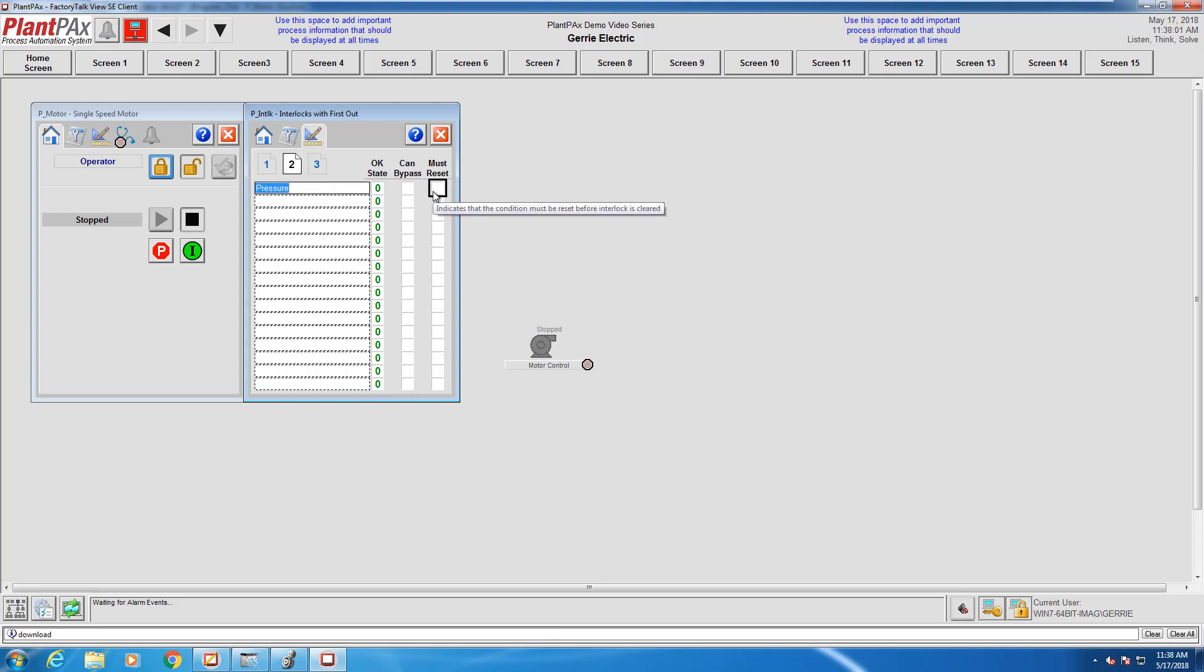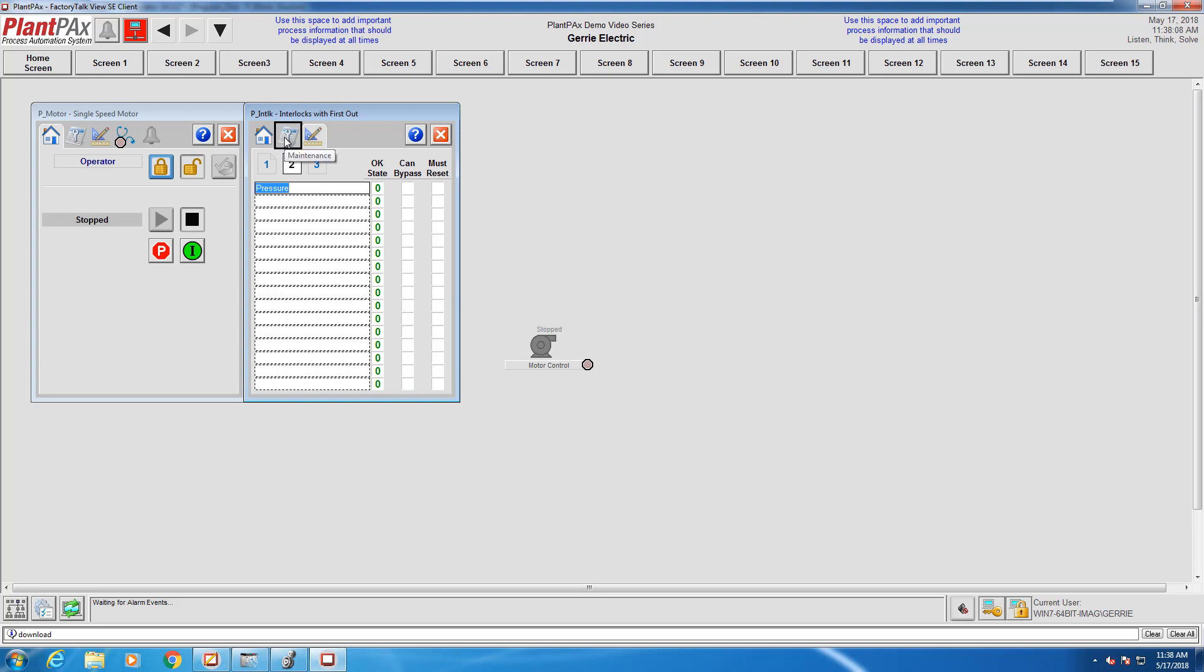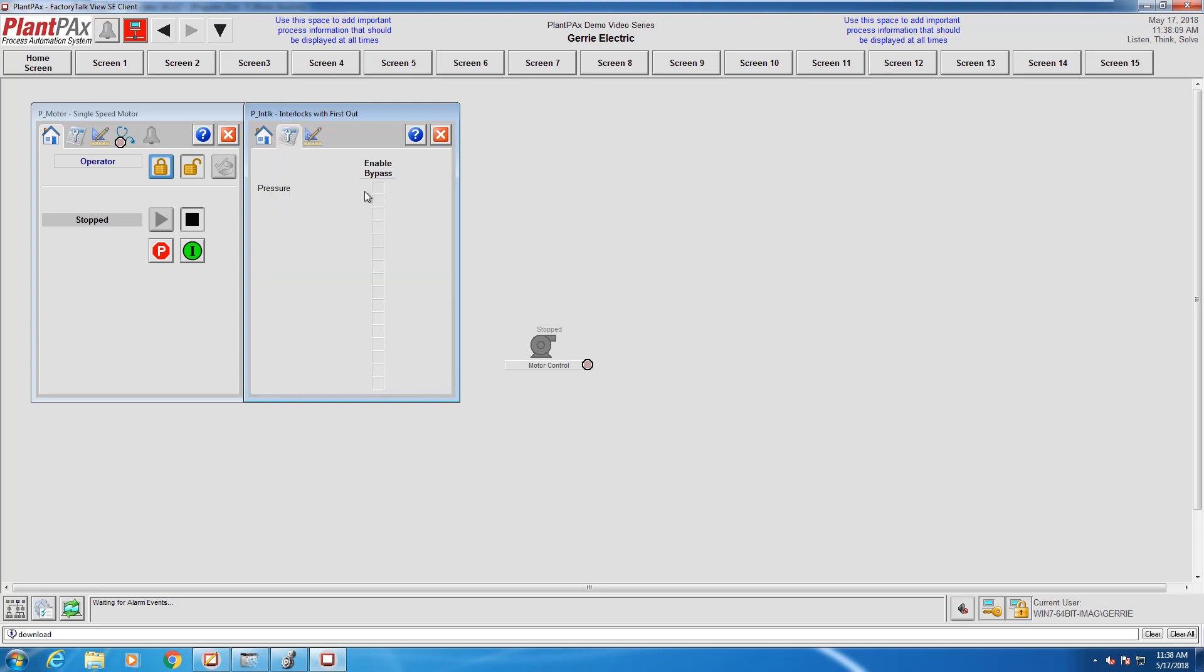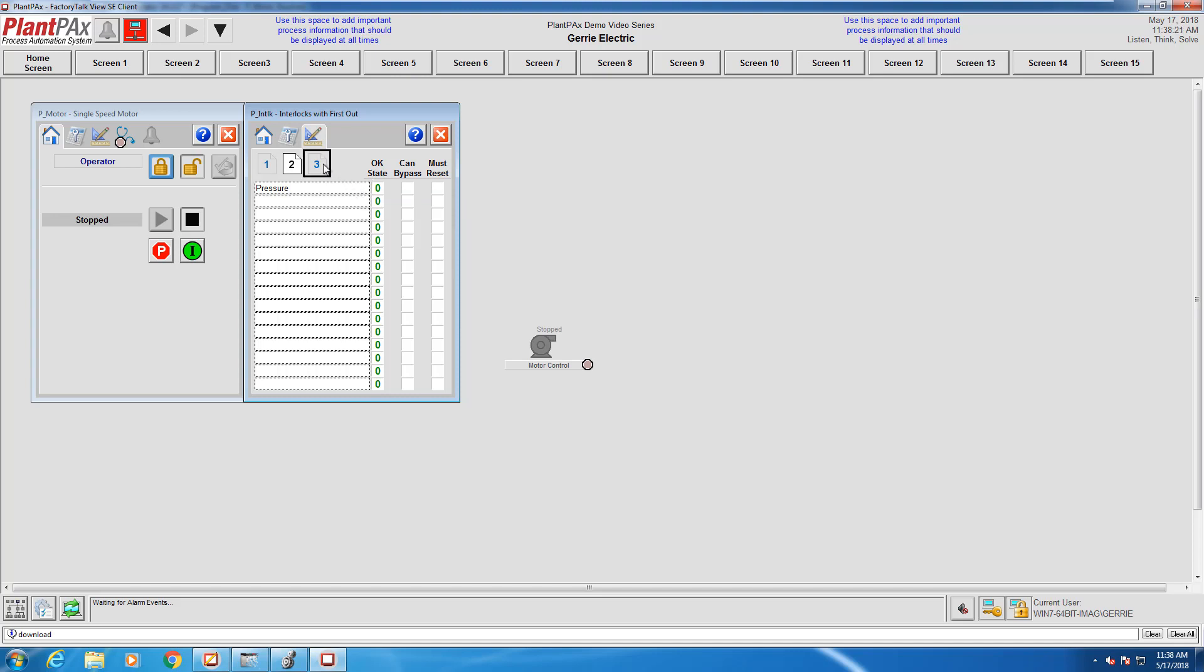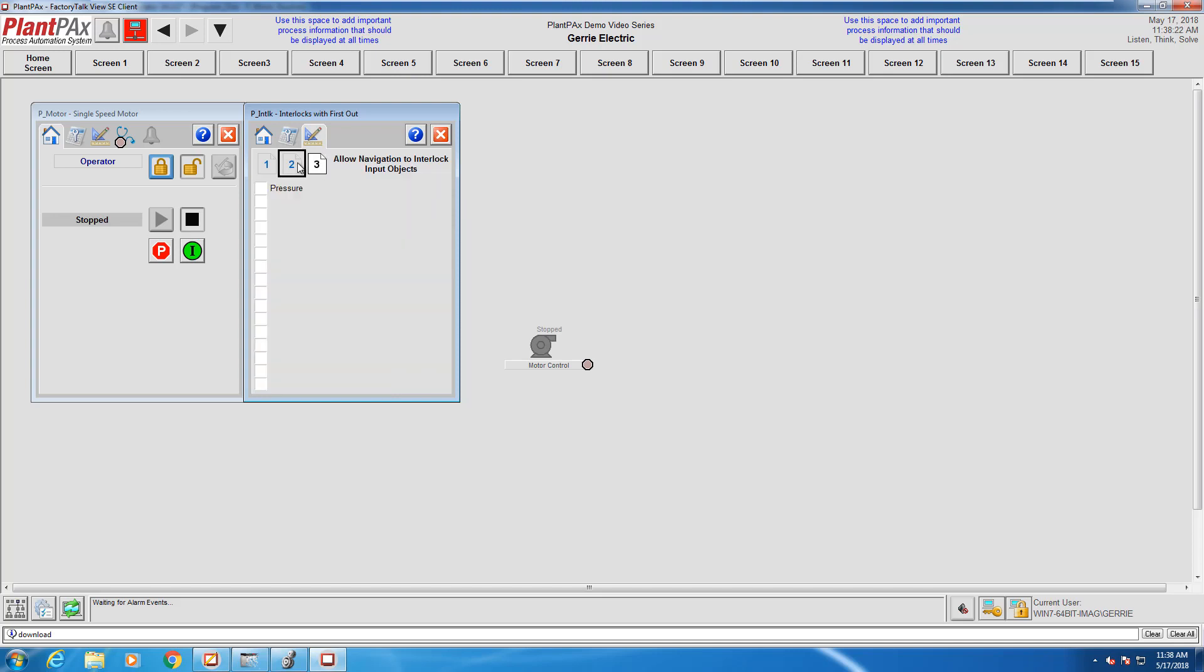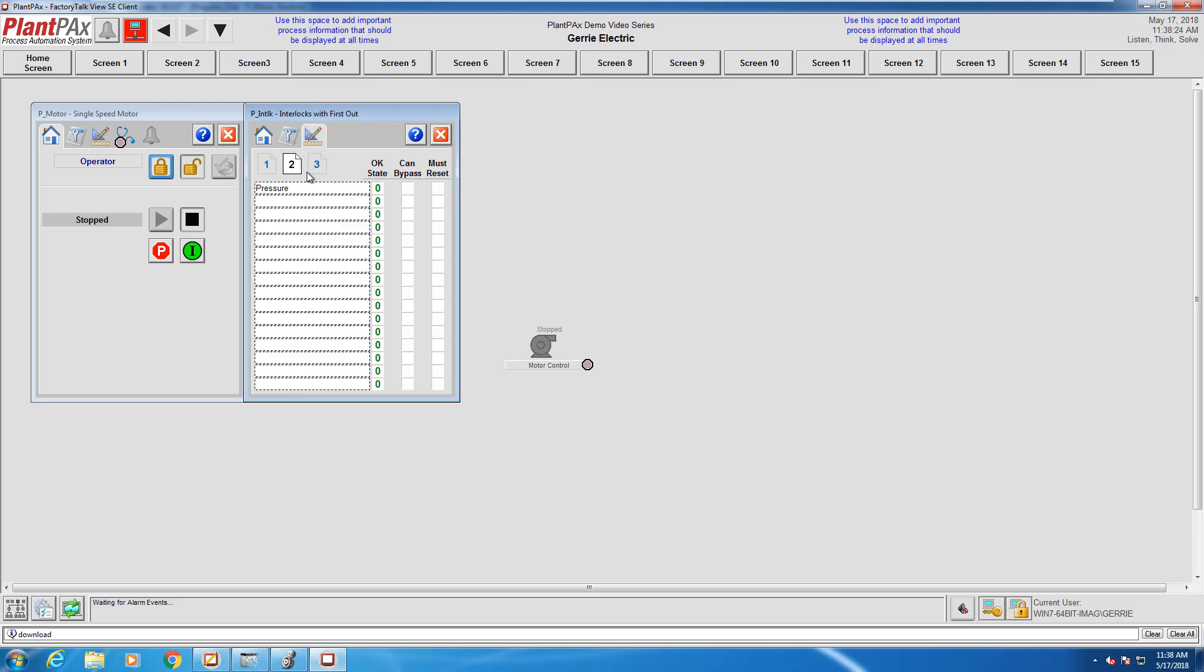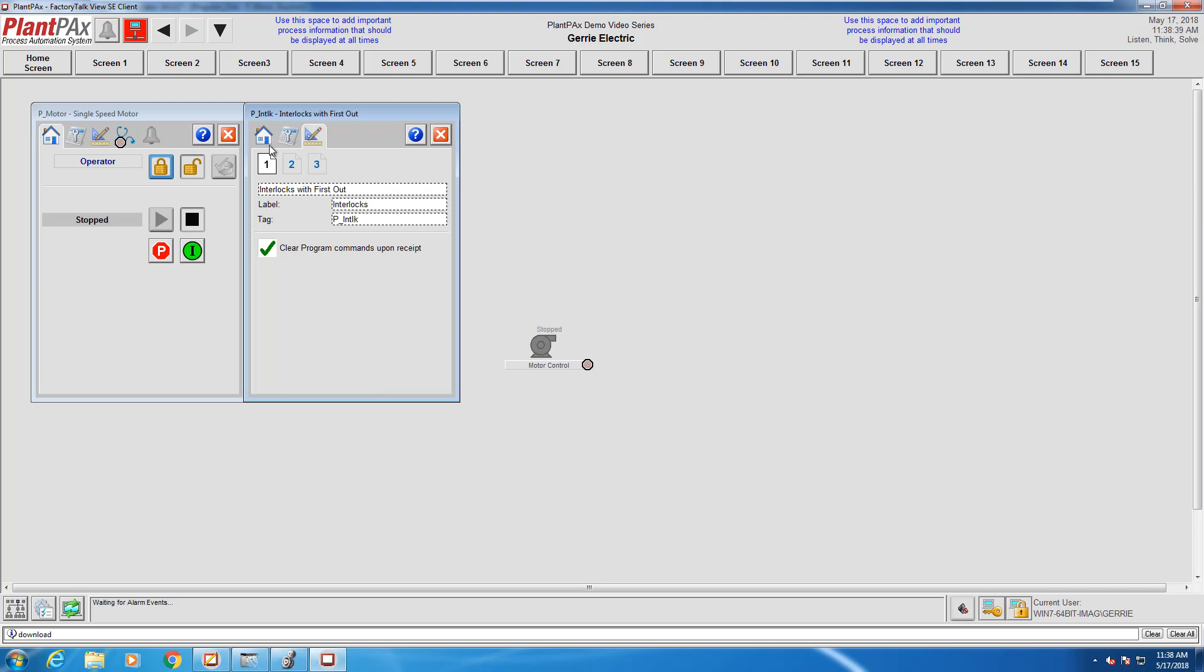Notice there's a couple of configuration options. Is this interlock bypassable? For example, when I log into maintenance mode, will maintenance be able to bypass this interlock or not? Another configuration parameter is the okay state—is a zero an okay state or is a one an okay state? That's configurable as well. The third thing is resets. Should an interlock trip occur, do you want an automatic or manual reset? When must reset is checked off, that means the operator needs to click into the motor block and actually physically reset the device before you're able to start the motor again.